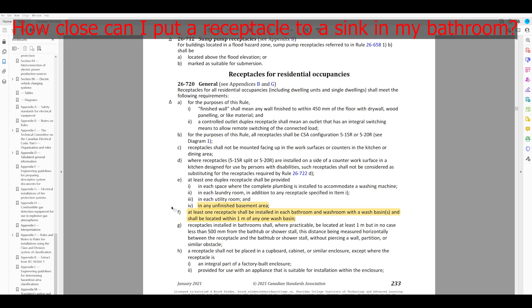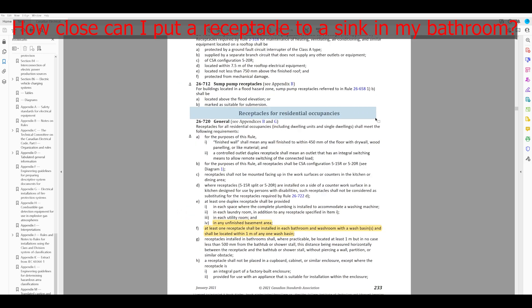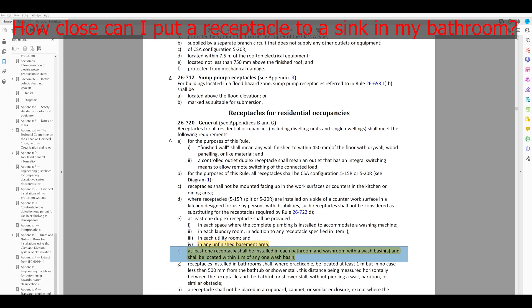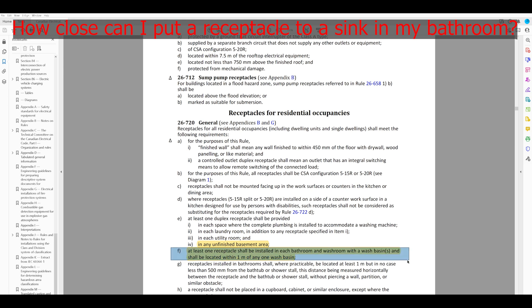We'll do 26-720 again. Right away I can see it — receptacles for residential occupancies. I'd start reading, looking for a measurement. Eventually I get to 'one meter': at least one receptacle shall be located in each bathroom and washroom with a wash basin, and shall be located within one meter of any wash basin. Wash basin equals sink. So this is telling me I need a receptacle within one meter.